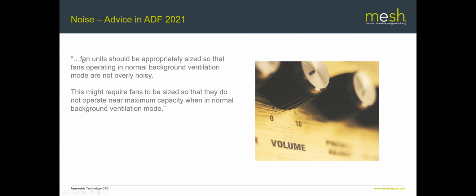Well, it says the fan unit should be appropriately sized so the fans operating in normal background ventilation mode are not overly noisy. This may require fans to be sized so they do not operate near the maximum capacity when in normal background ventilation mode.